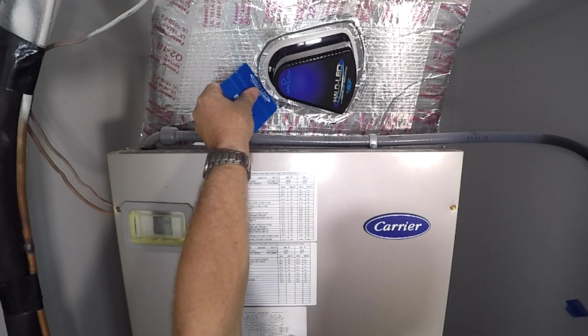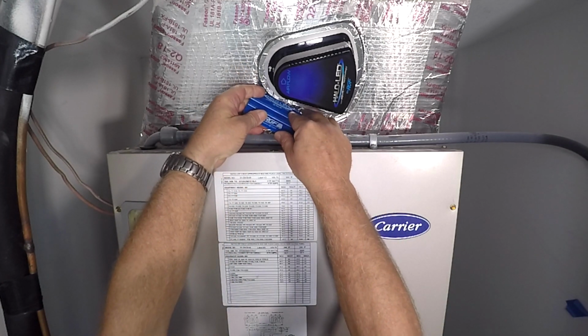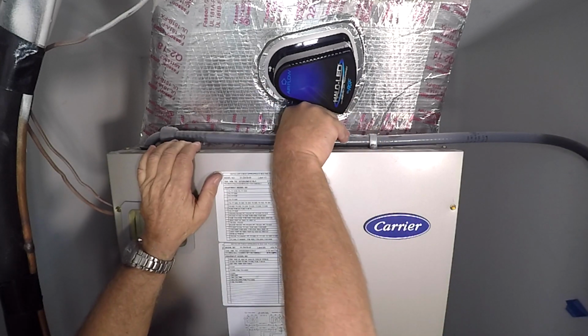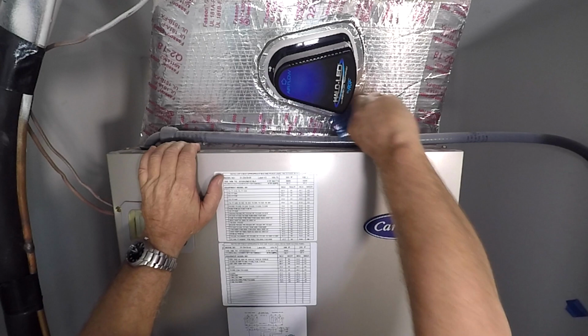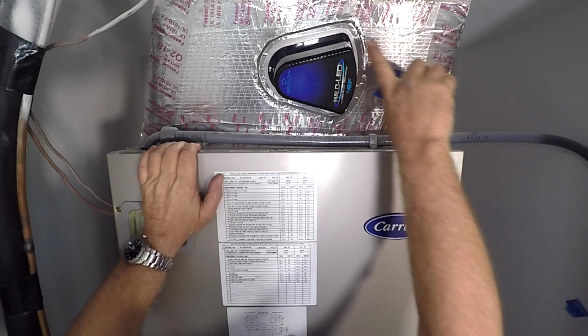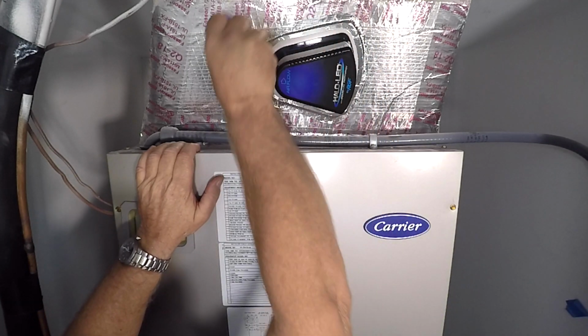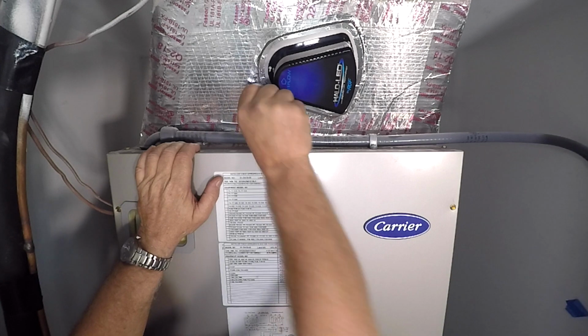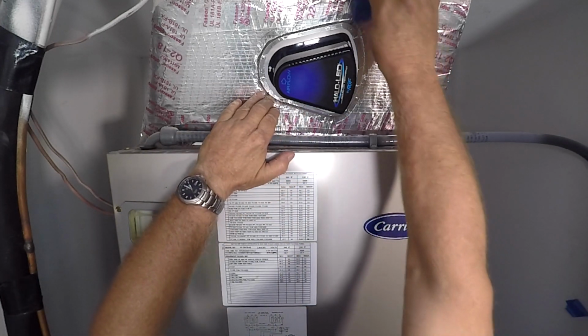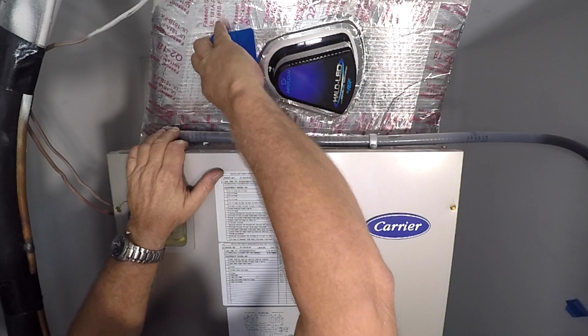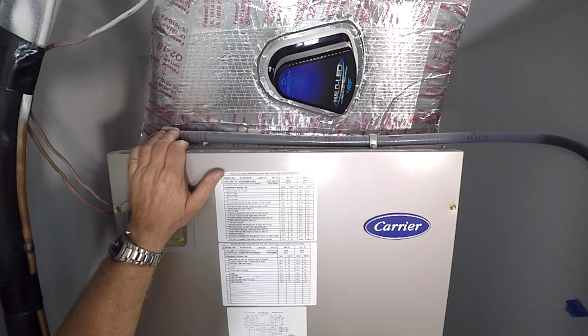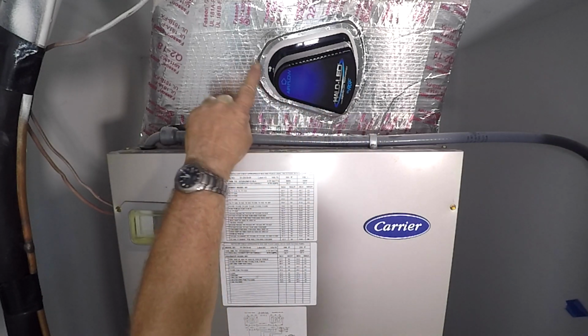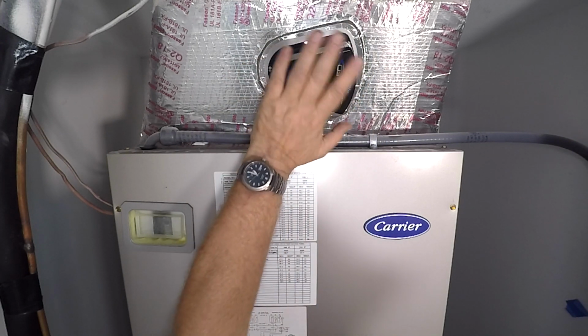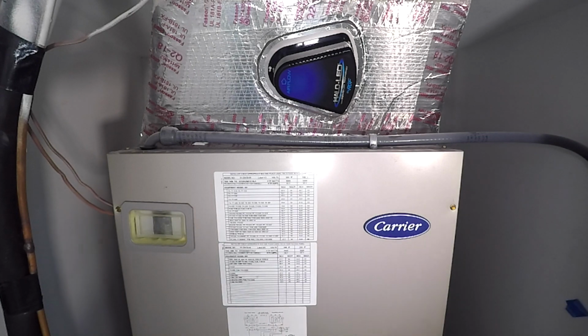On this type of ductwork, you do not need to use any type of screws or whatnot to seal the unit, as the aluminum tape and the gasket will hold it perfectly fine. On metal ductwork, however, you may want to use the 3 screw holes around the unit, here, here, and here, to mount it to your metal ductwork for a more secure fit and install. You can, however, do the same type of install with your metal ductwork. Try to keep your aluminum tape clear of the cover, because the cover does remove if you need to service the unit, and you do not want the metal tape getting in the way of the unit.